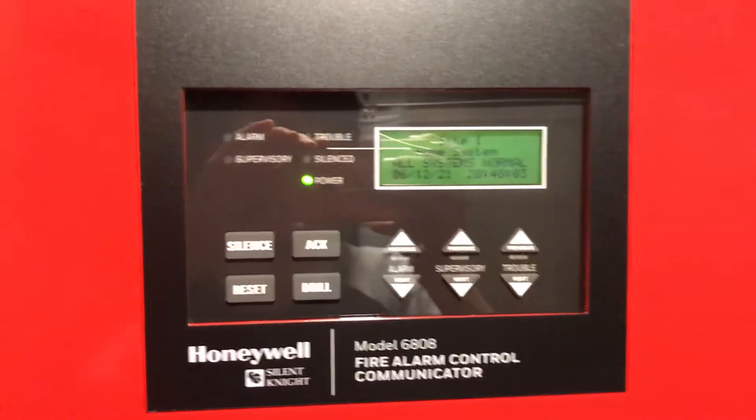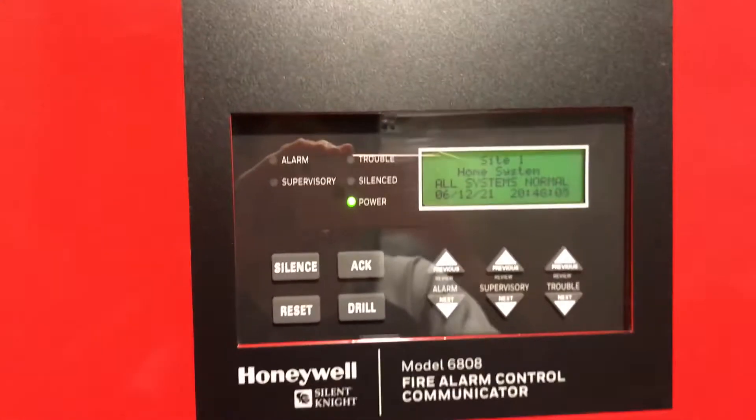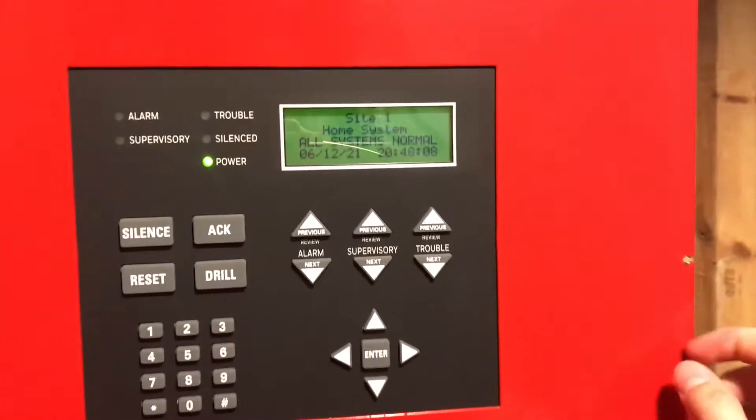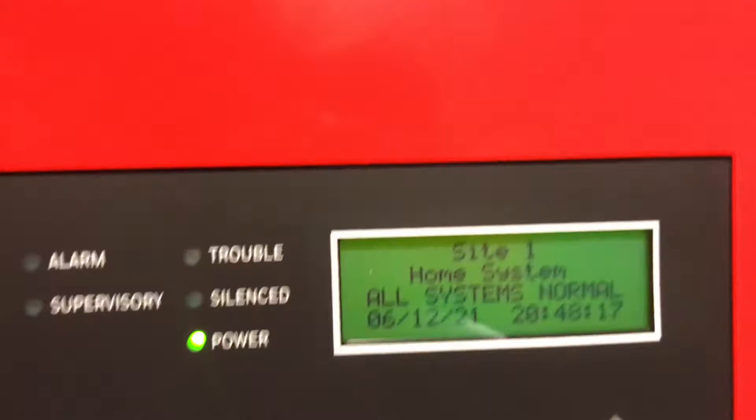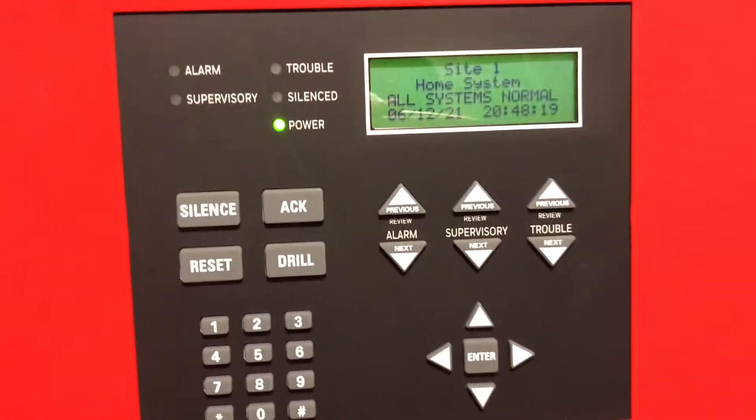This is going to be the first test of the Silent Knight 6808. I don't have any addressable devices or modules for this panel, so I can only test the fire drill function. I did program the NACs, but I have not programmed the relays yet. I have the NACs synced and everything.